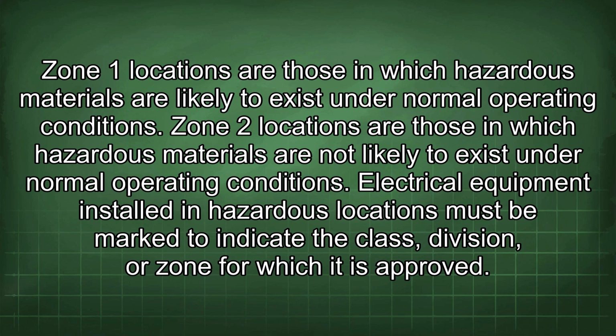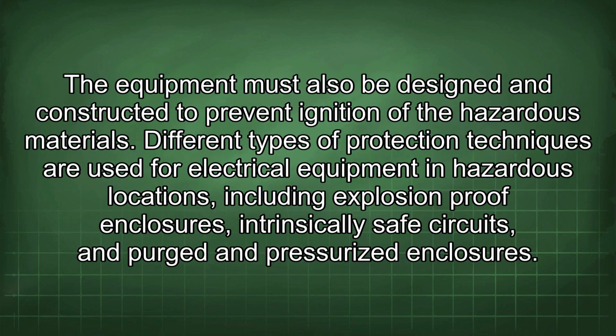Electrical equipment installed in hazardous locations must be marked to indicate the class, division, or zone for which it is approved. The equipment must also be designed and constructed to prevent ignition of the hazardous materials. Different types of protection techniques are used for electrical equipment in hazardous locations, including explosion-proof enclosures, intrinsically safe circuits, and purged and pressurized enclosures.